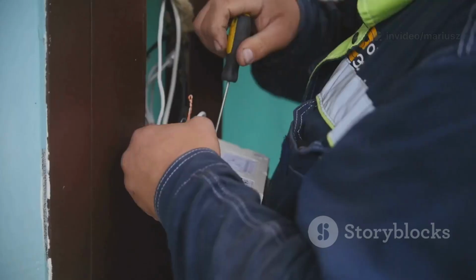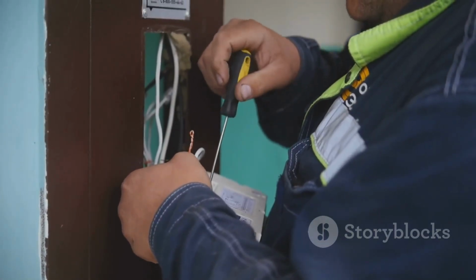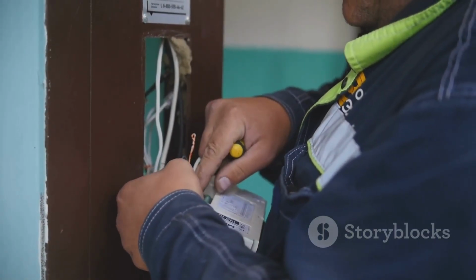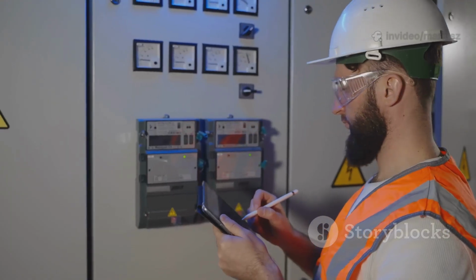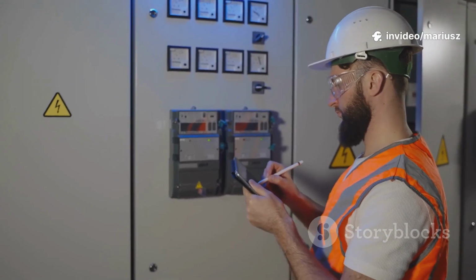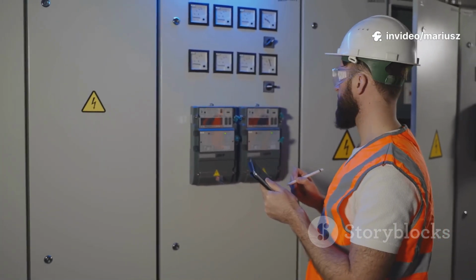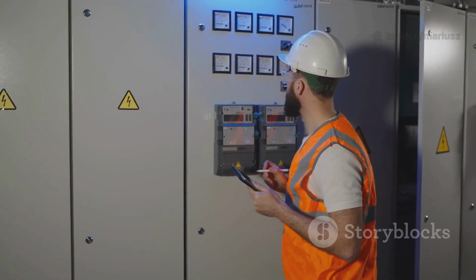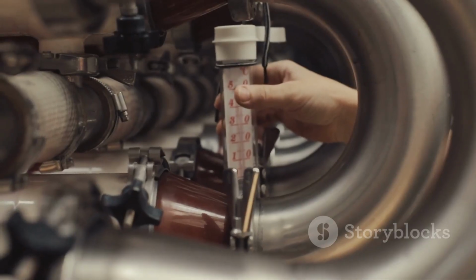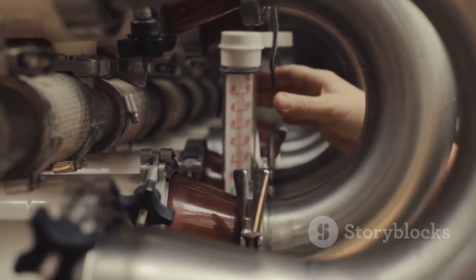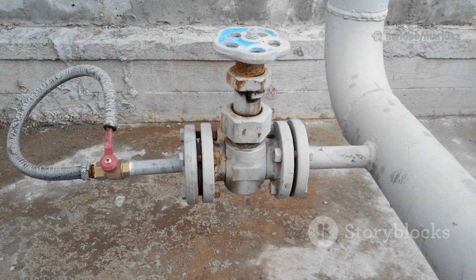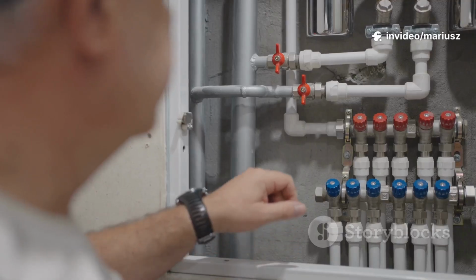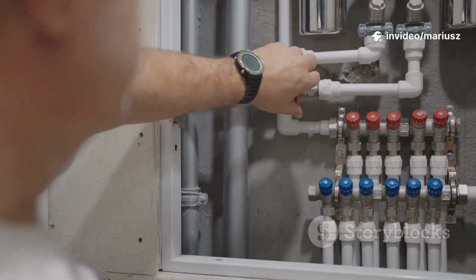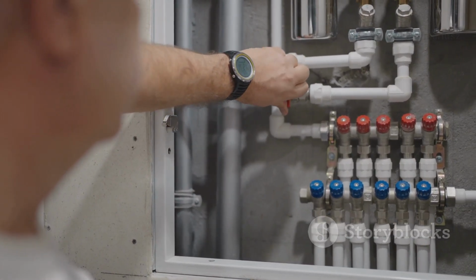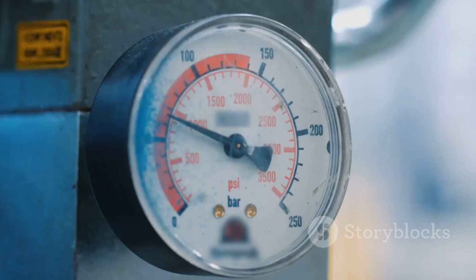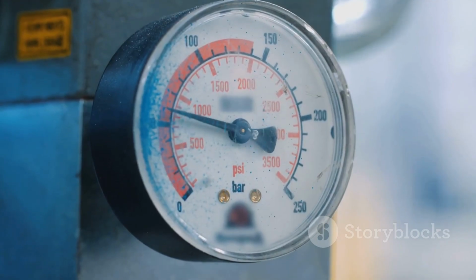Earthing. After isolating the motor, we connect the electrical conductors to the ground using special earthing equipment. This ensures that any residual charge is safely dissipated, and that the circuit cannot become live if it's accidentally re-energized from another source. Similarly, if we were working on a pipe that contained high-pressure steam, isolation would mean closing valves on either side of the work area, but we'd also have to perform venting, opening a drain valve between the closed valves to safely release any trapped pressure. Only when the pressure gauge reads 0 is it safe to proceed.